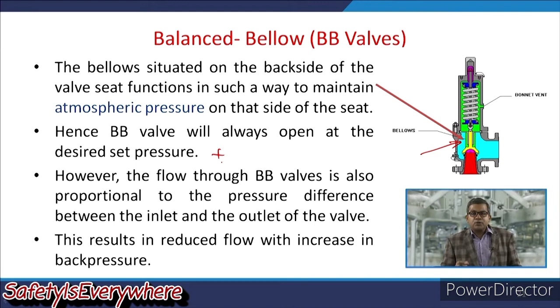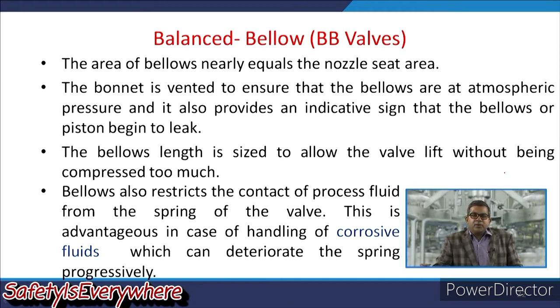The area of bellows nearly equals the nozzle seat area, this one. The bonnet is vented to ensure that the bellows are at atmospheric pressure, and it also provides an indicative sign that the bellows or piston begin to leak. The bellows length is sized to allow the valve lift without being compressed too much. The bellows also restricts the contact of process fluid with the spring of the valve. This is advantageous in case of handling corrosive fluid which can deteriorate the spring progressively.